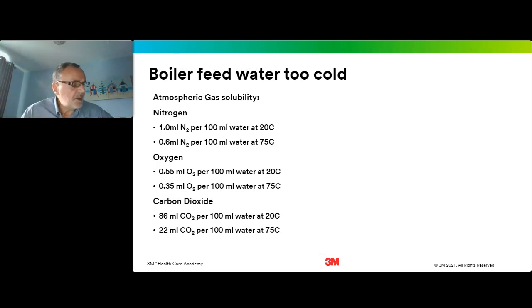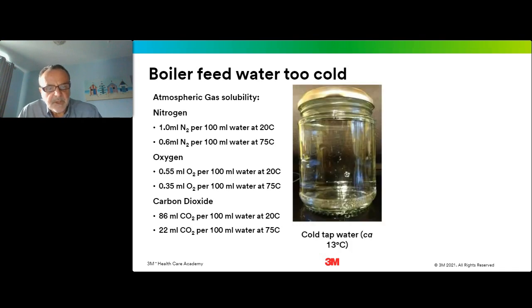So if we look at the problem of the boiler feed water being too cold, on the left-hand side of the slide, you can see the solubility of atmospheric gases in both cold water and hot water. Nitrogen will dissolve 1 mL per 100 mL, oxygen 0.55, and note that carbon dioxide is very soluble in cold water. And you can illustrate just how much gas is dissolved in your water.